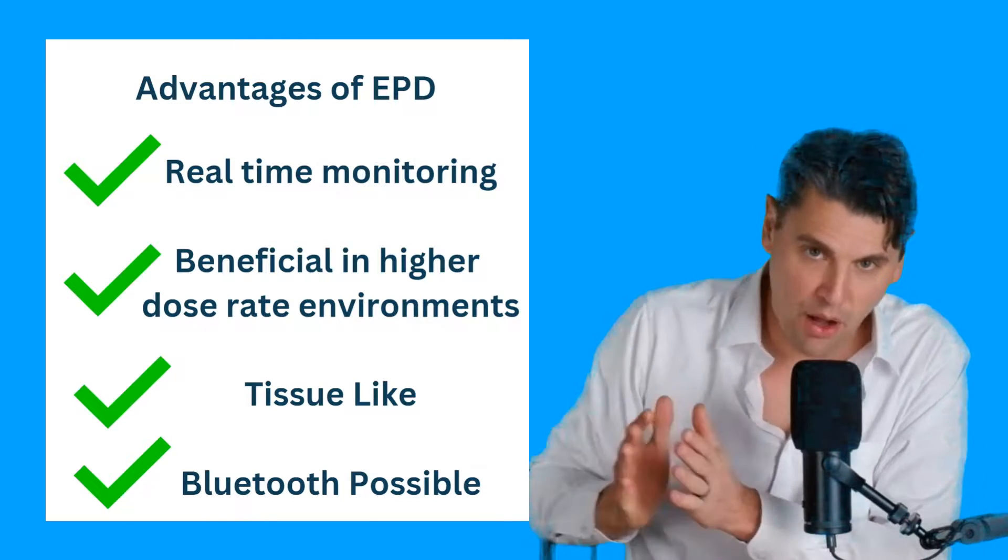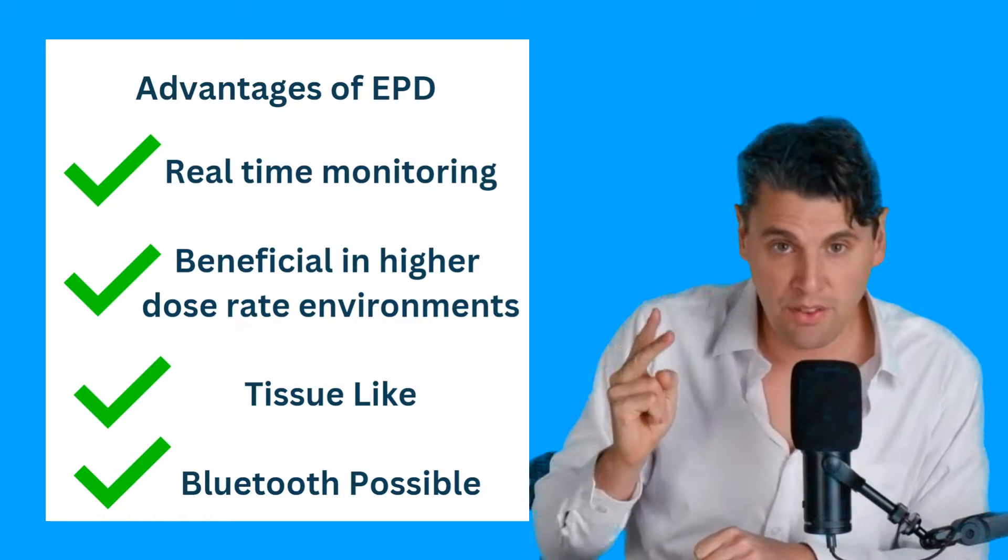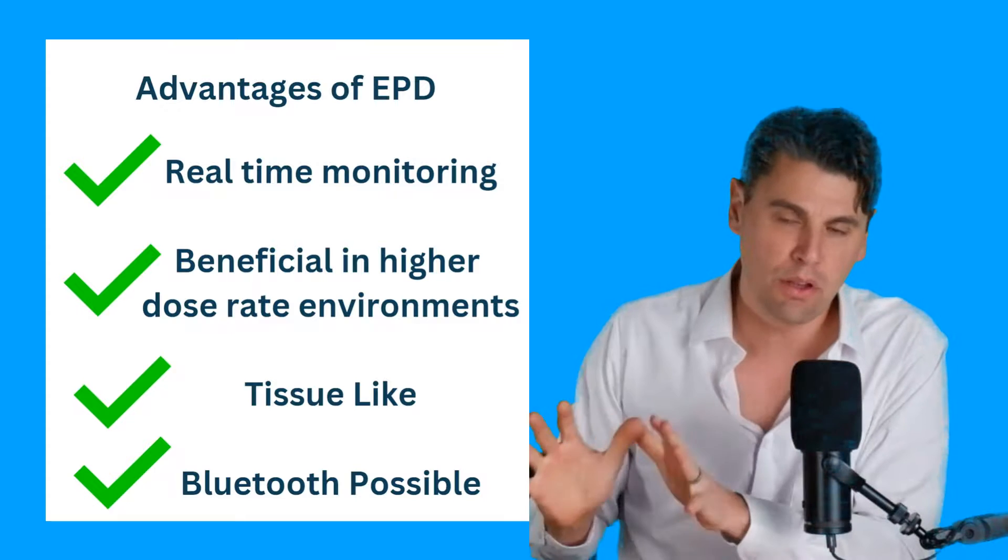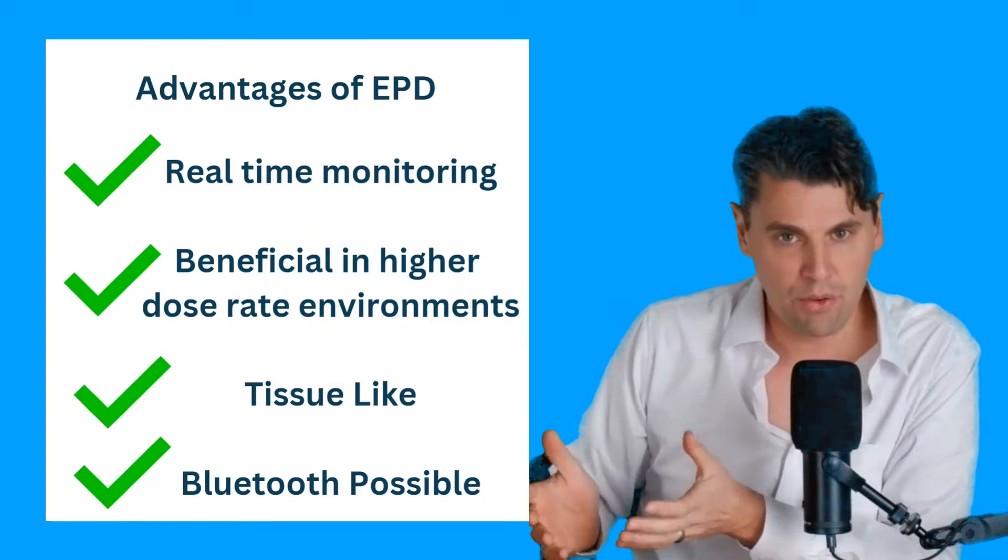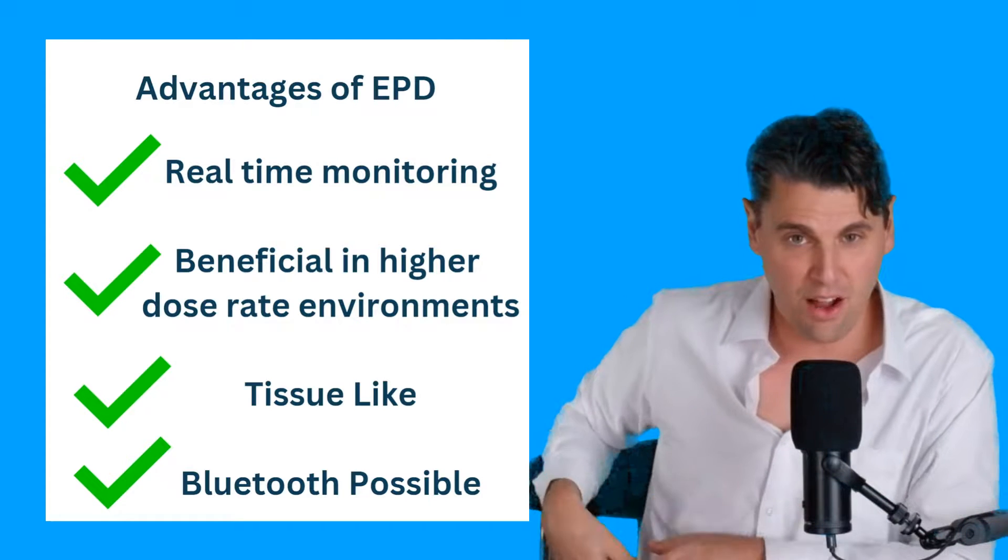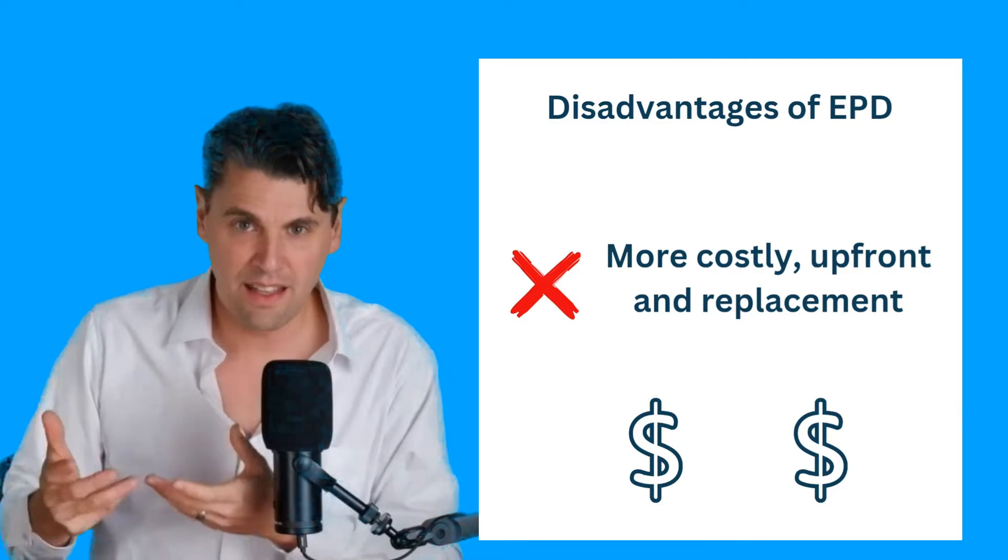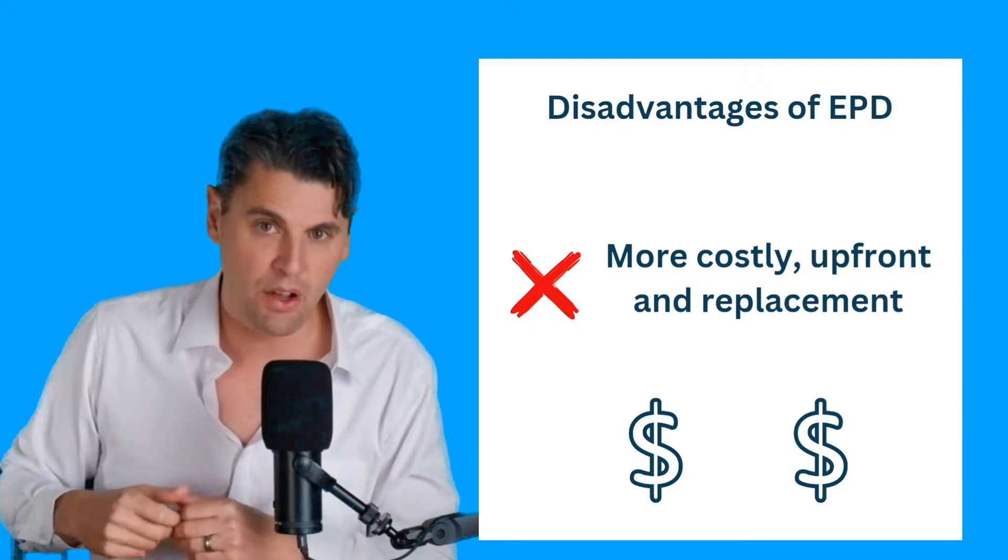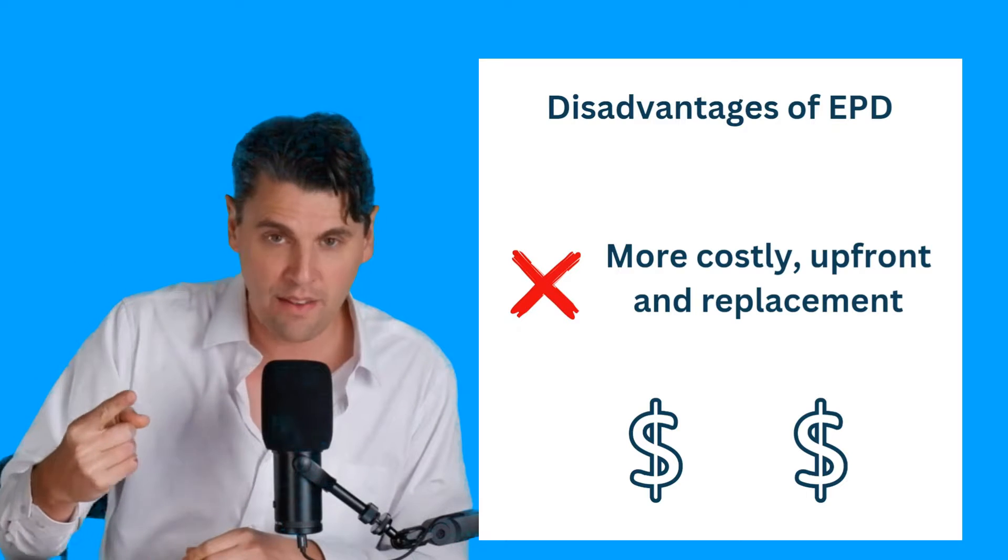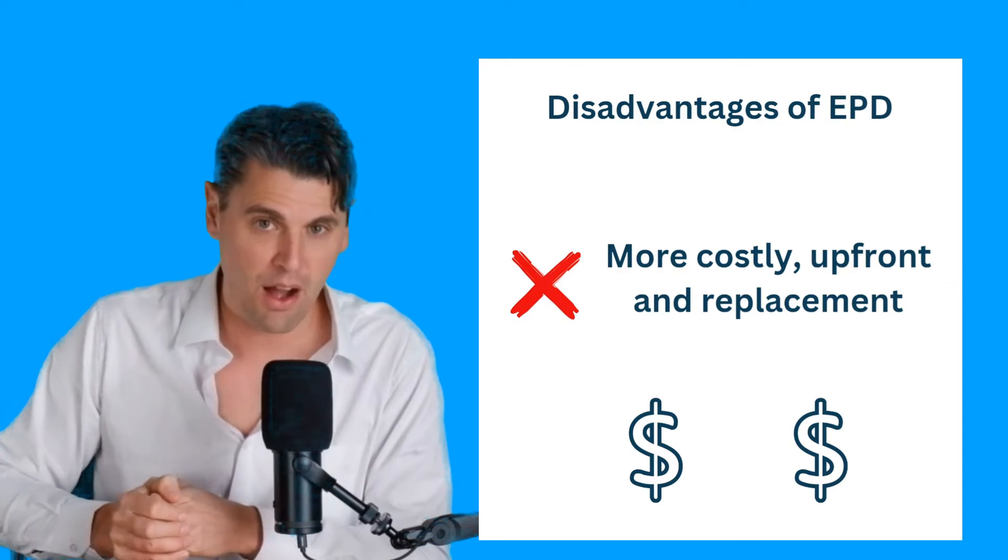The advantages is, in comparison with all the other techniques that we've talked about, it's real-time monitoring, so you don't have to send it away. It benefits from scenarios when you have a higher dose rate environment, and you'd like to monitor in a more real-time what the dose is in these environments. It's tissue-like. Nowadays, it can be Bluetooth-capable. They can actually send off the dose to another device, and then can be tracked automatically in that manner. Disadvantages is the cost. These are more expensive than any one of the technologies I've talked about so far. This is from both an upfront cost, and then also a replacement cost. So if you as a technologist lose one of these, then you would have a replacement cost for this device.